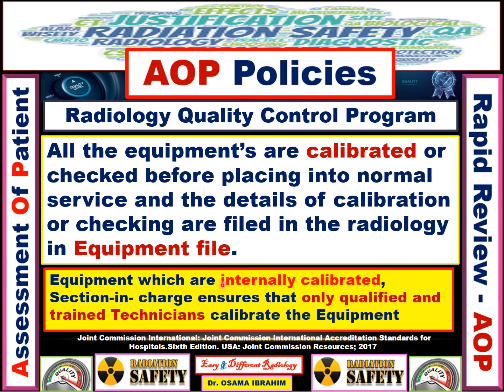For equipment that is internally calibrated, the section in charge ensures that only qualified and trained technicians calibrate the equipment daily, or according to the timing ascertained in the department. Each individual department has its own time for internal calibration of the machine before use.